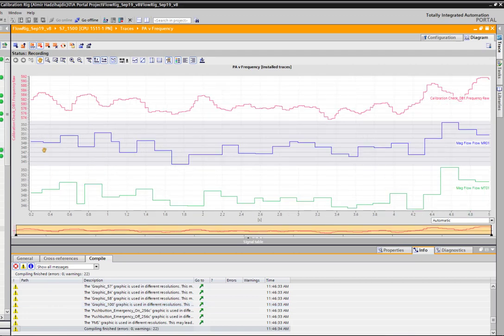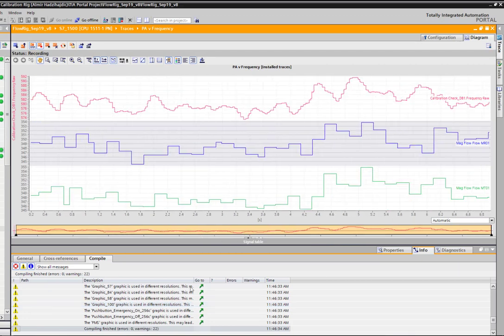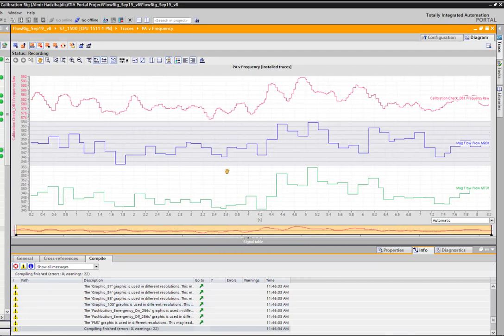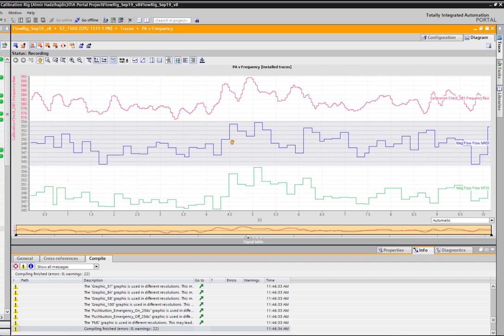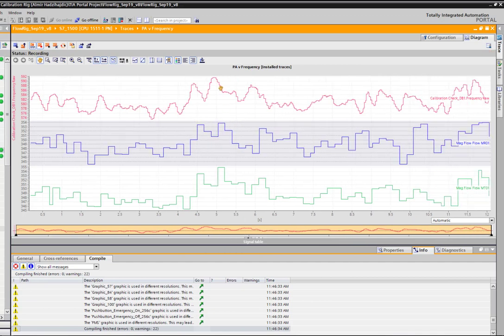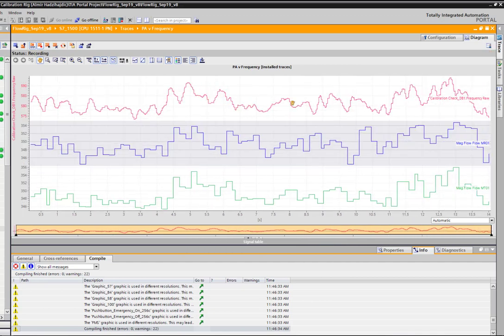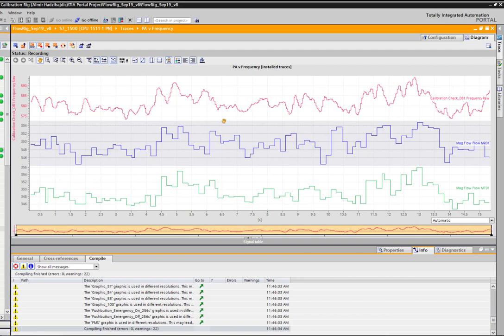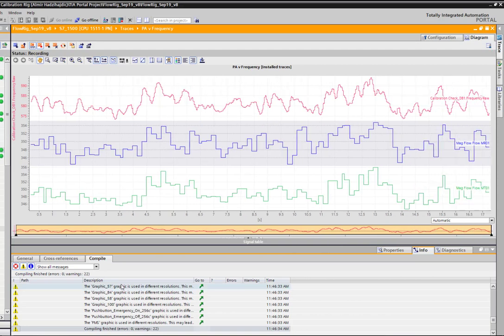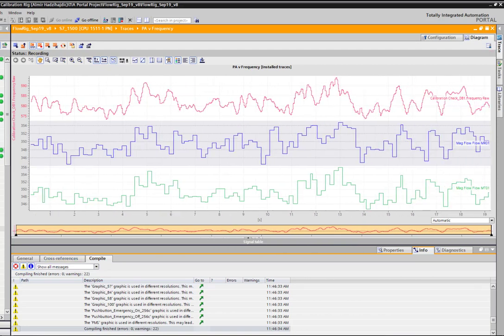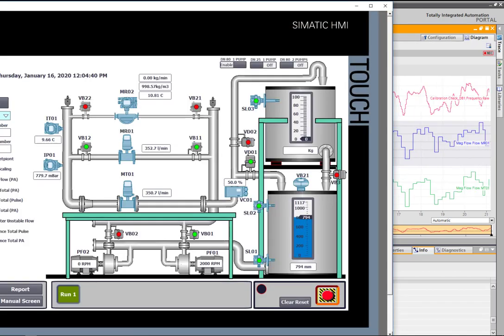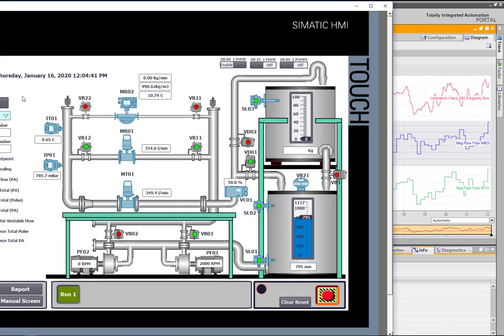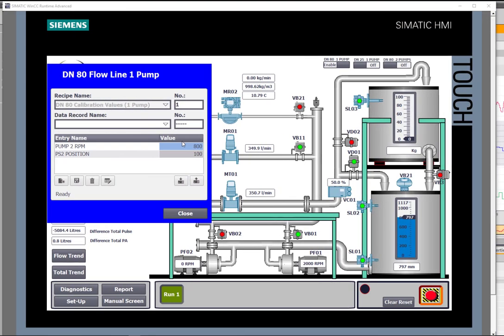The scale is auto scaling but hopefully you can start to see now how the PROFIBUS PA value is performing to the high speed counter. So it is lagging behind a little bit. Let's put some step responses into this to get it working a little bit better.